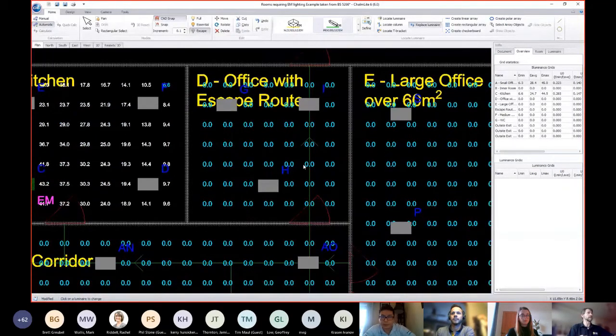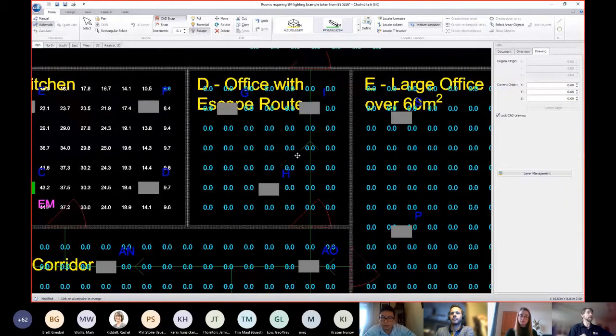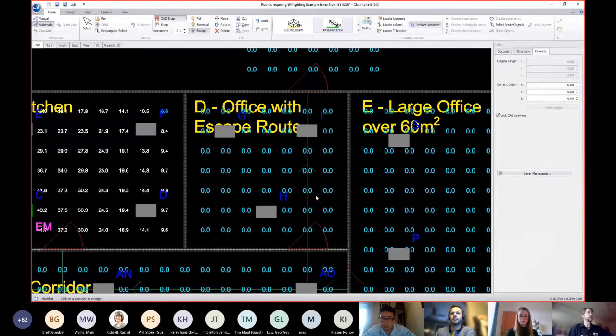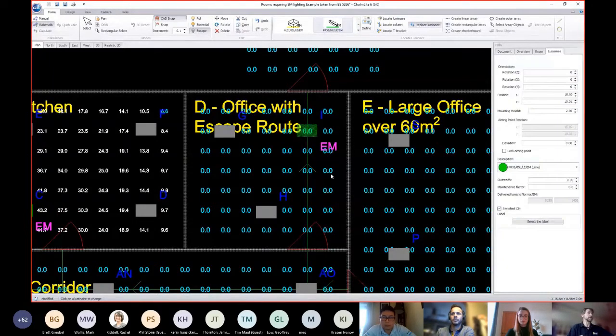Now, here's another room. It's a little office, and it constitutes part of an escape route. So we'll absolutely need to put some emergency lighting in here, close to the escape door. And we can see we're getting 1.1 as our minimum. That's lit to emergency standards.